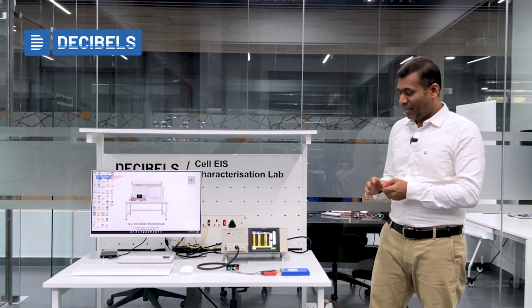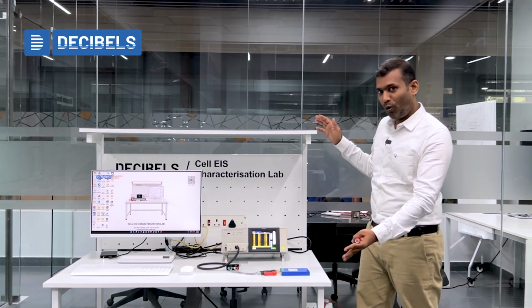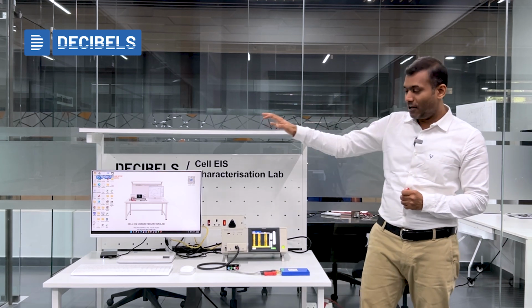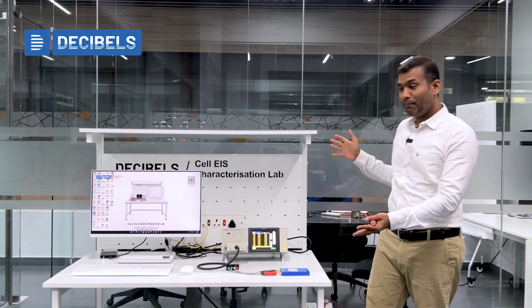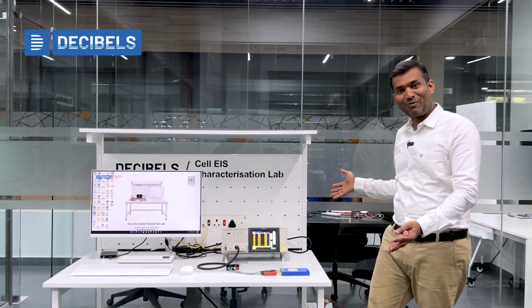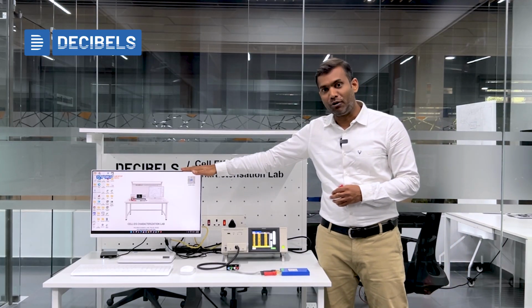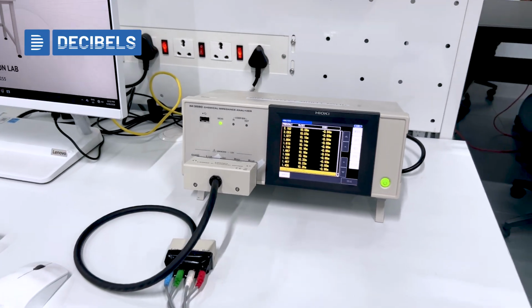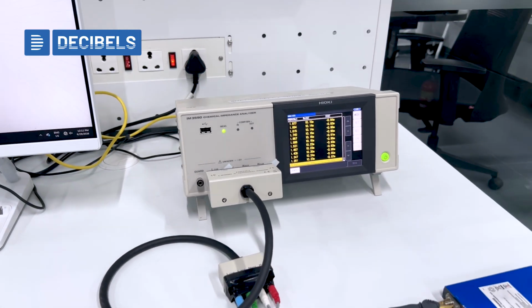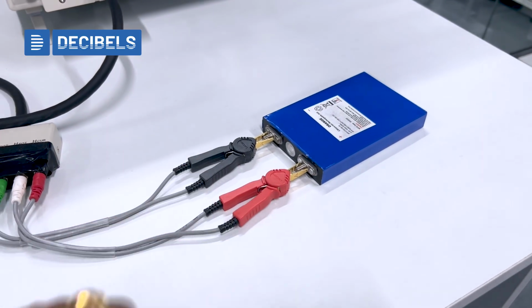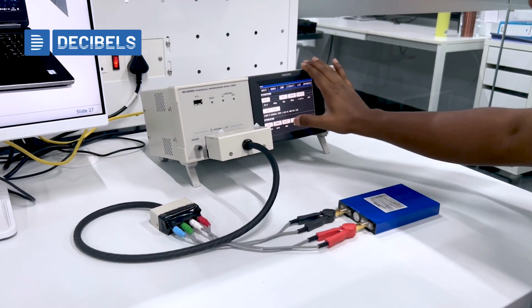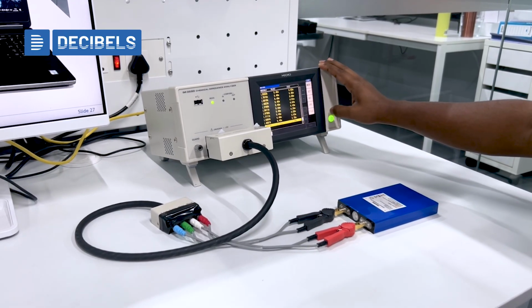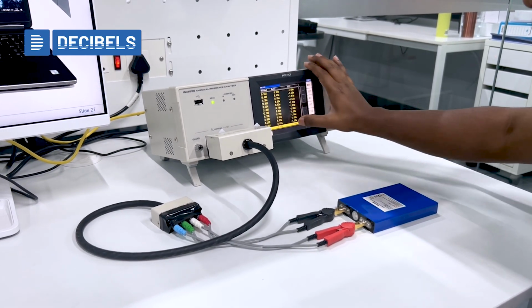Before we go in depth into how all this happens, this whole lab setup comes with several instruments. First is the complete fixture that lets you keep all the instrumentation, and then we have the computer that can acquire the data from the test instrumentation, and then the test instrumentation itself is sitting here on the table, and then we have the device under test, which is also sitting here on the table. So we get several connector options depending upon if you want to test a cylindrical cell, a prismatic cell, or a pouch cell.